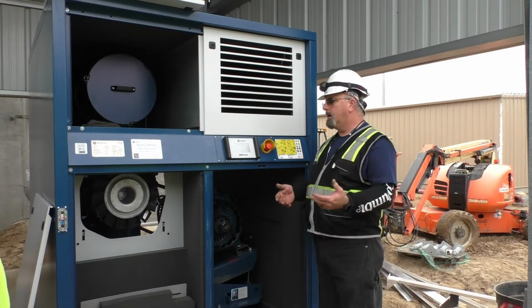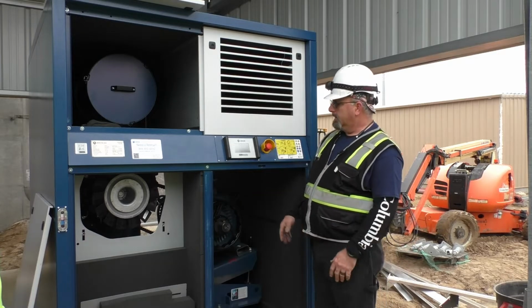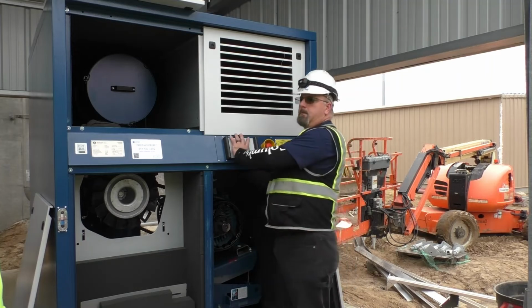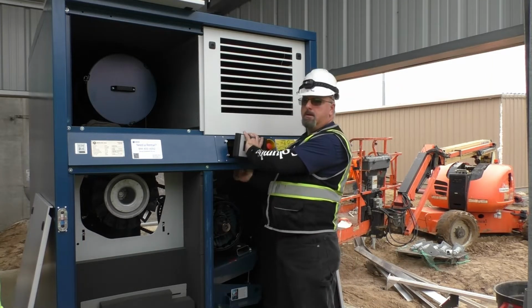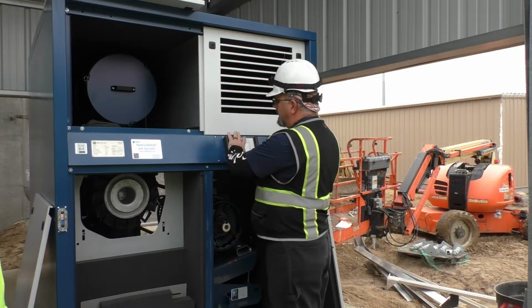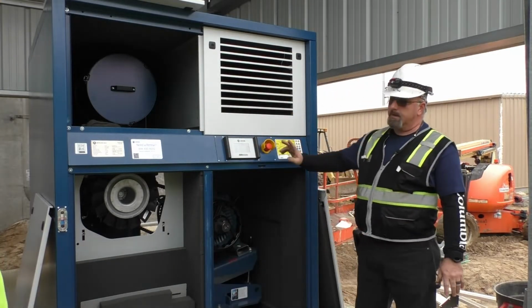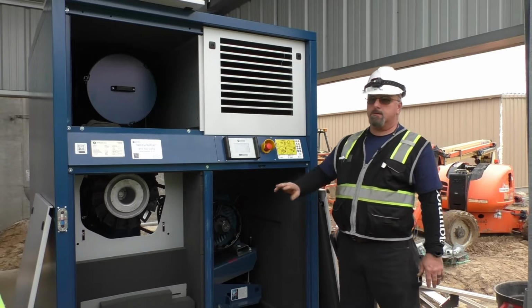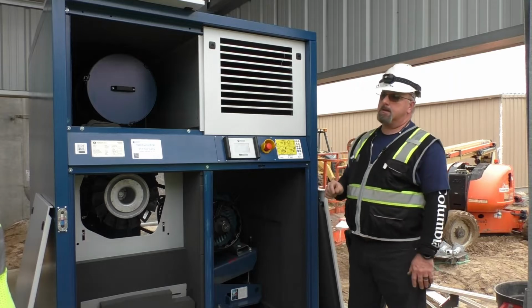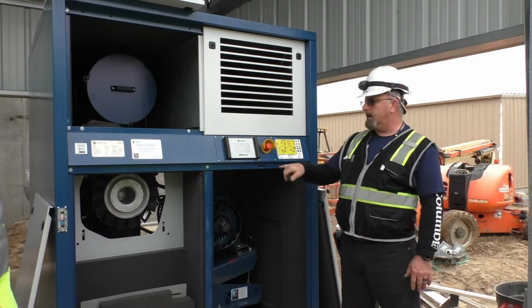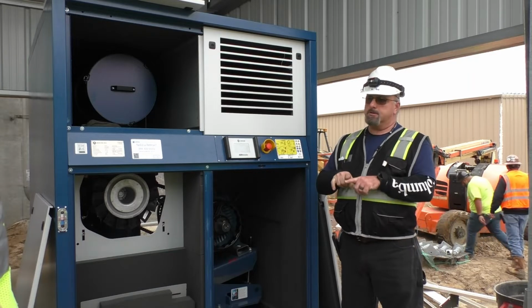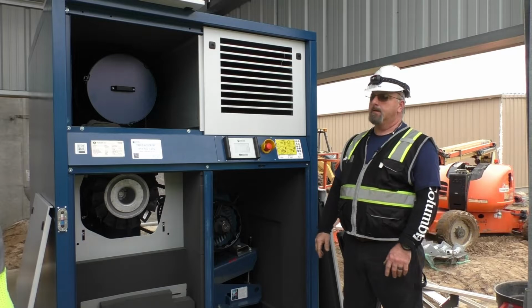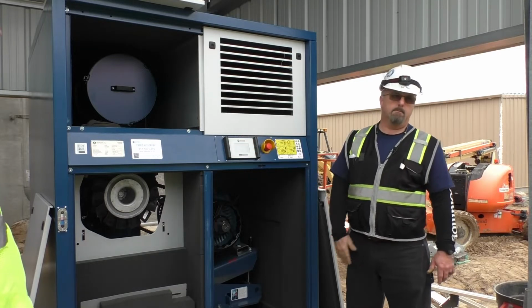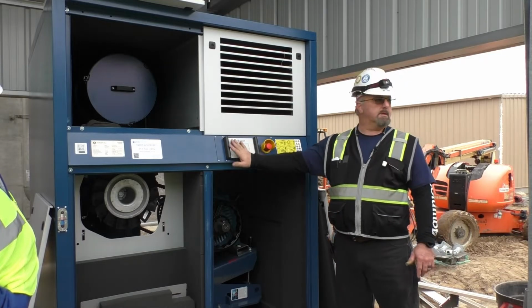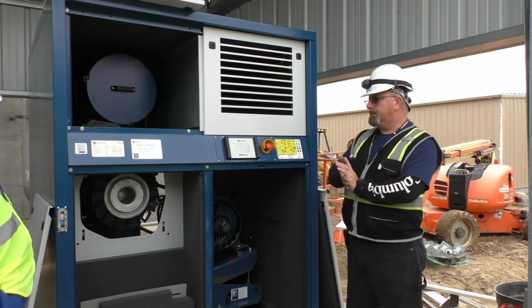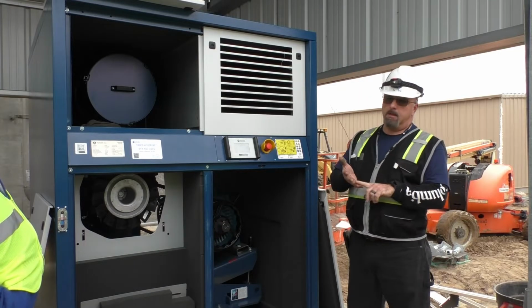They come as a kit with instructions to install, but basically you just pop this off. Be careful when you pop it off so that it doesn't damage this connector back here. Install your cover. Now the one thing I will say, if you ever have to replace this or you get those covers, do not disconnect this plug with control power on, because what will likely happen is the 24 volts that powers this will short across pins and you'll kill it. So turn control power off when you mess with this. Any other questions on this right here? I mean, the book will walk you through every menu, how to get to it, what it is, what it includes.